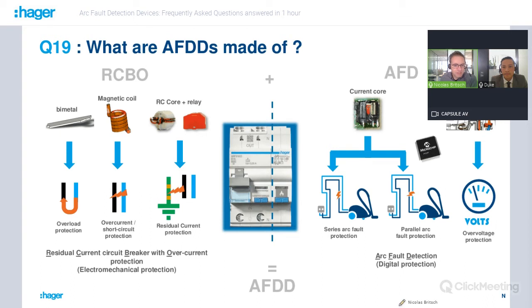If we talk about the RCBO plus AFD, we will have the same components on the MCB part, which are the bimetal and the magnetic coil for overload protection and overcurrent short circuit protection. But we will also find something else, which is dedicated for the residual current protection: residual current core, and relay, electromechanical relay. And on the AFD part, we will find the same components as before, but the only difference is that we don't use the GF core, as the function of neutral crossing will be ensured by the RC core, which is located on the left side.